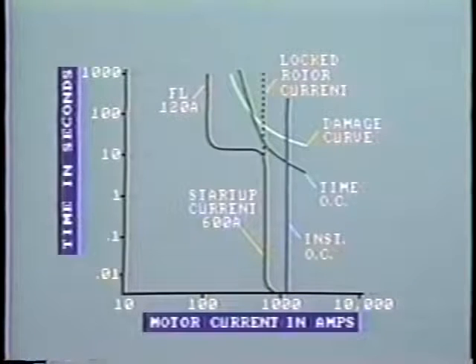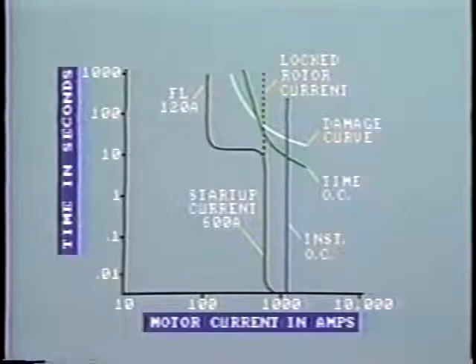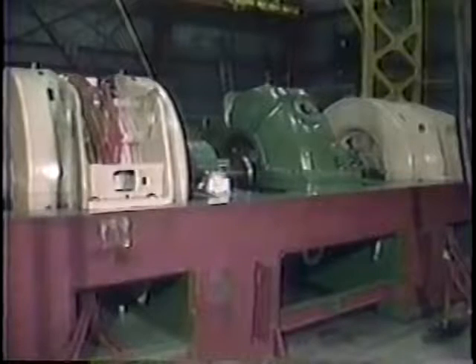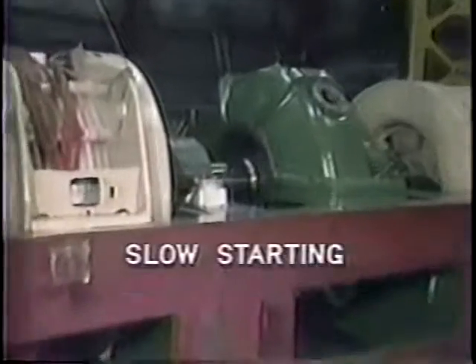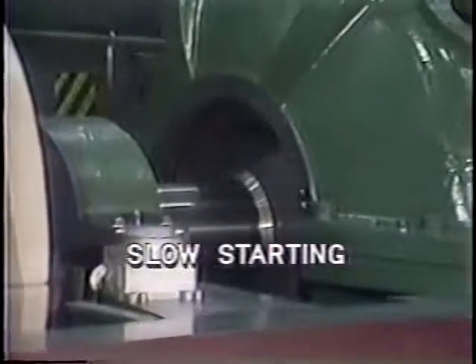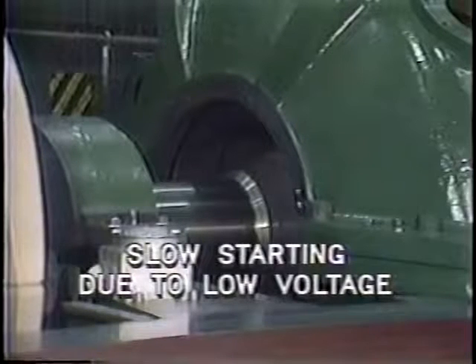But this is not so easy as it appears. Remember, the induction relay will pick up as soon as the motor is energized and high locked rotor current flows. Even though the current level falls off, the relay may still time out and trip, usually around this point. The solution is to allow more tolerance by slowing down the relay. It may also trip if the motor takes longer than usual to start up. For example, this could occur if the supply voltage is low.